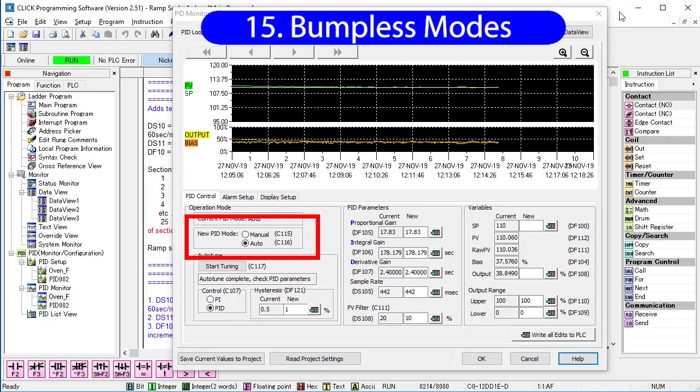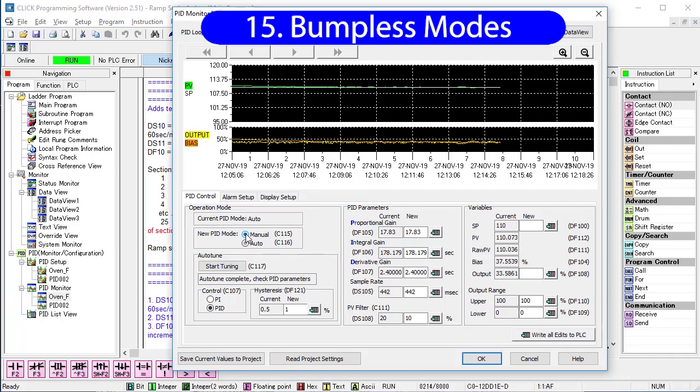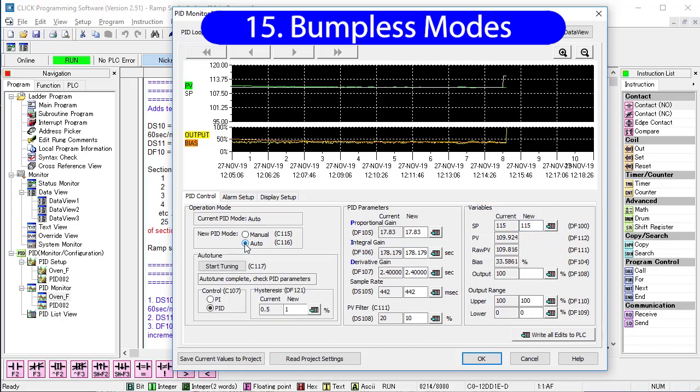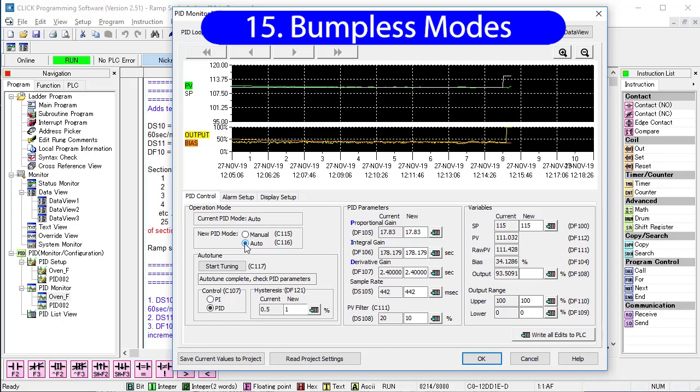When you switch from manual mode to auto mode, what happens to the process? Let's switch to manual mode. Move the set point away from the process variable and then switch to auto mode. And, as expected, PID goes to the max output to try and get the process variable to the set point as fast as possible. In our temperature demo that's no big deal because things move so slowly. But, if you have a fast moving massive machine, going straight to full output when switching to auto mode could be dangerous or it could damage the machine.